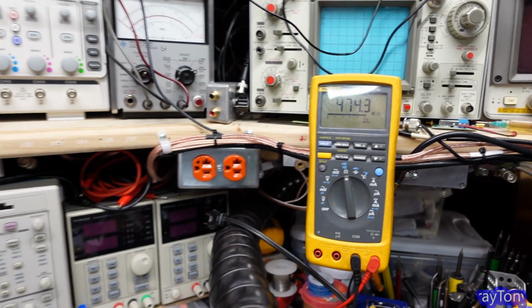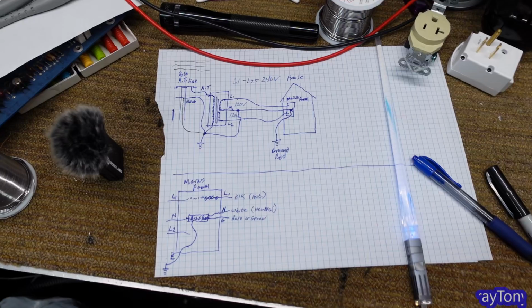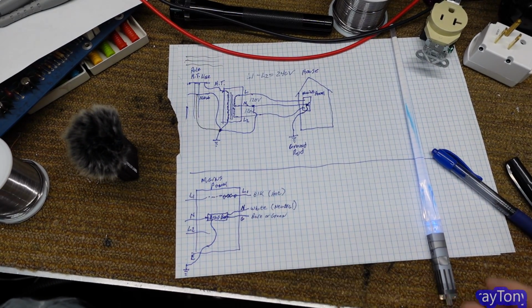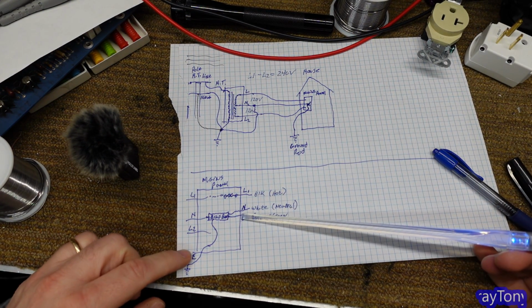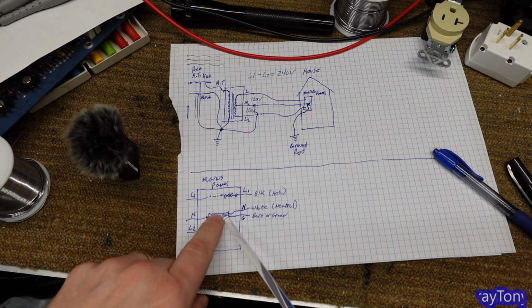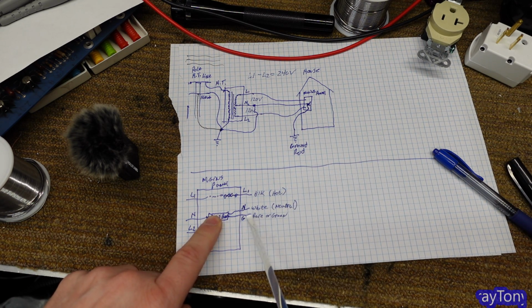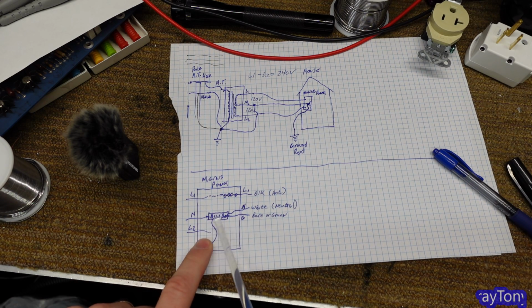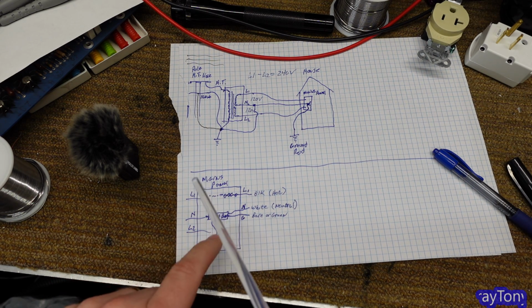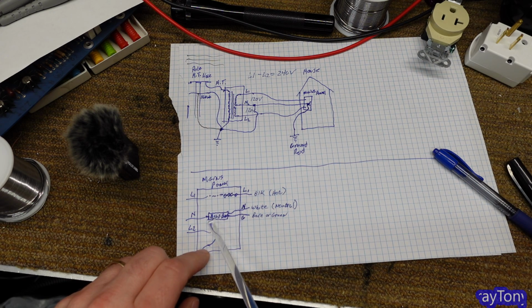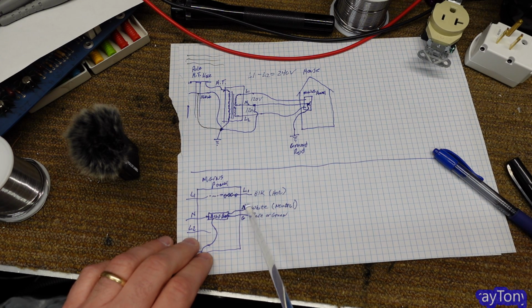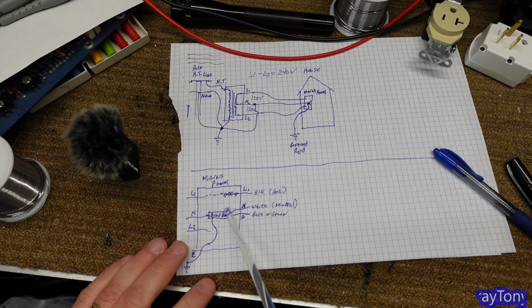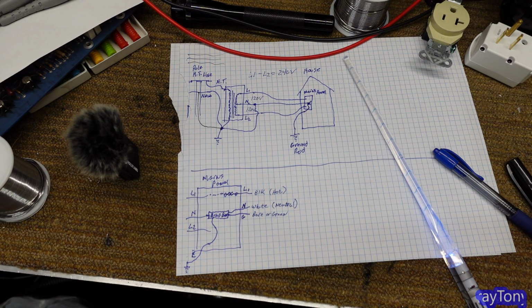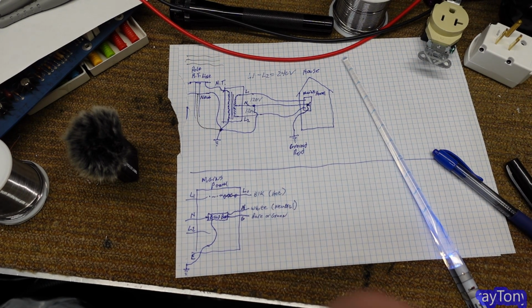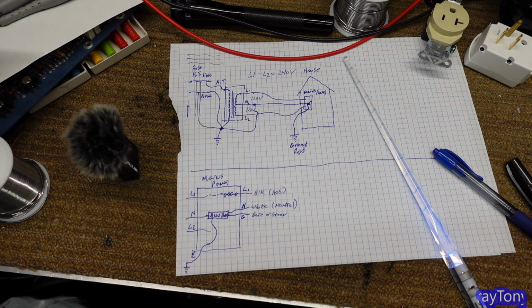In addition to that, if you look back down here, ground and neutral are bonded together in your mains box. So all the way through the ground, it'll come back to this bus bar, and anything connected to that terminal on my oscilloscope is also connected to the neutral of my incoming mains. Now, why would that be a problem? Well, this is where it gets interesting.